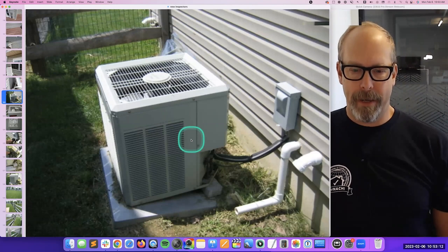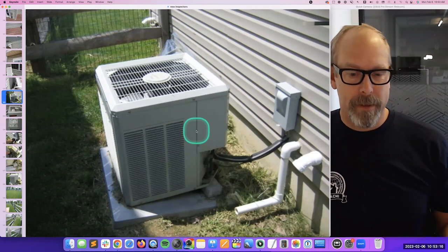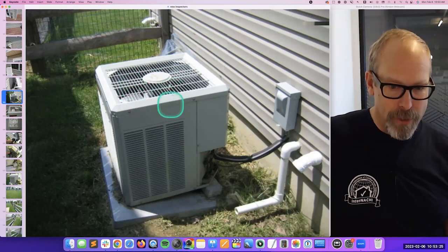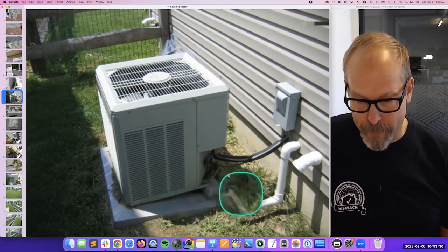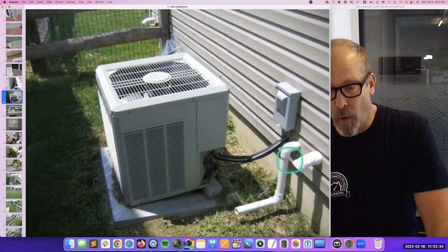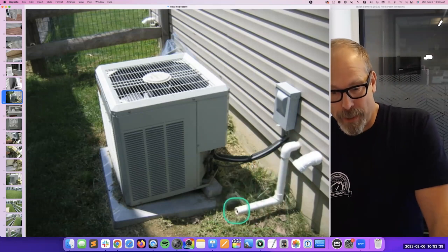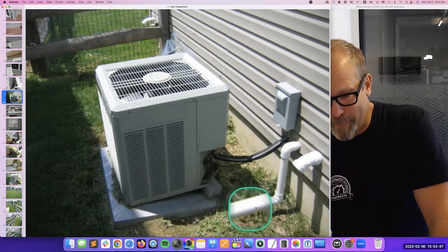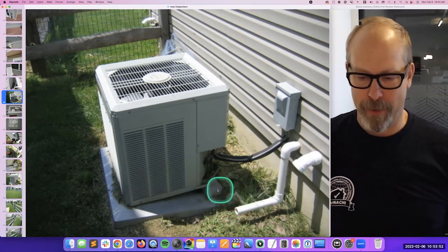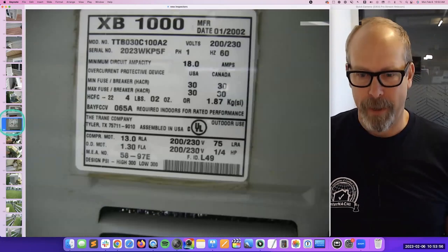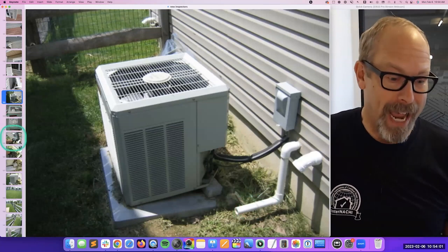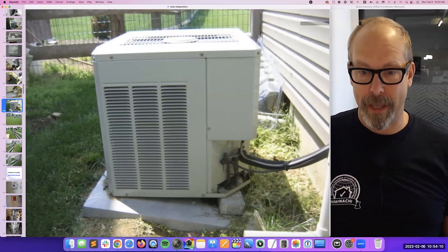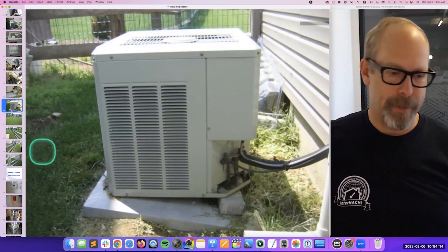Another system on the exterior — this is the air conditioning system, or it could be a heat pump. You can call it the exterior compressor or condenser. It looks like it's settled — the base settled up against the house and they stuck a couple of bricks under there. I bet it's because of that discharge from the sump pump — a ton of water discharge right here gets everything soft and starts to settle. Instead of fixing the problem, they just put a brick underneath it. So you can help people find out what the real problem is and recommend a solution that's actually going to work. There's the electrical disconnect, the refrigerant line, and the unit.